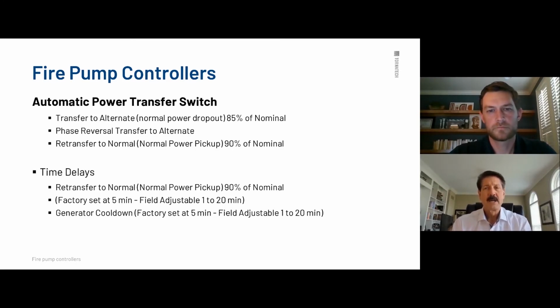And then what happens is, as he had mentioned, once the genset reaches 90% of nominal voltage, it checks to ensure that we're in sync at 60 hertz and that there is no phase reversal, as he mentioned on that side. We have to get up to 90% of nominal voltage, and in sync at 60 hertz, or again, if the phase reversal alarm goes off, it will not transfer over.